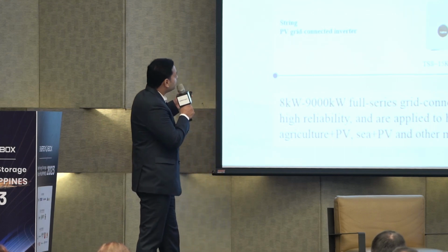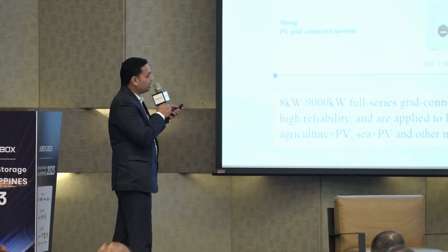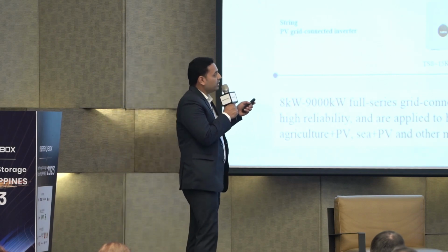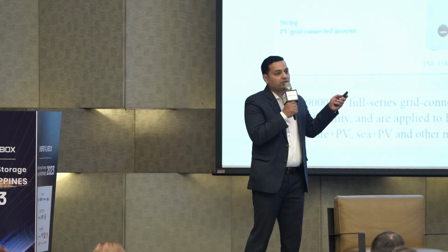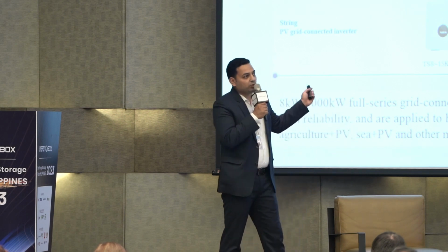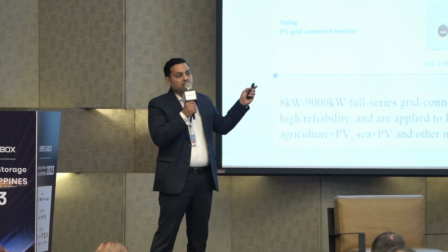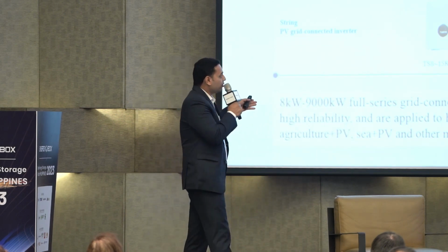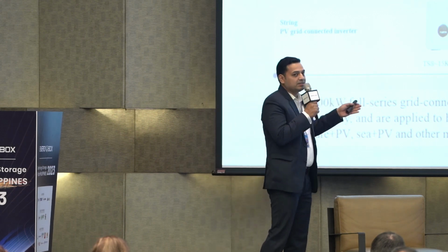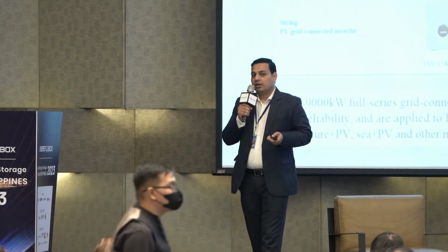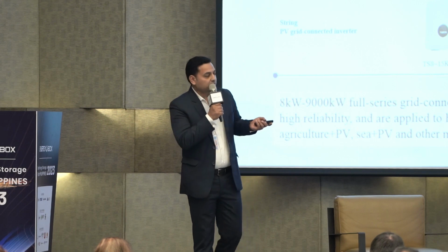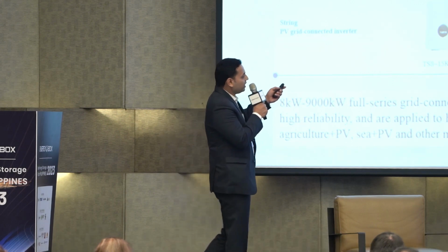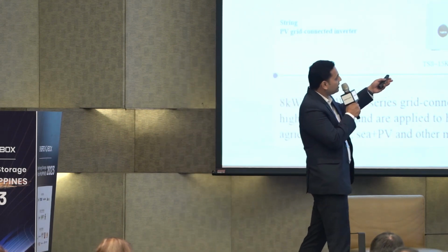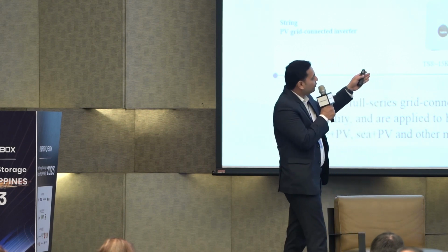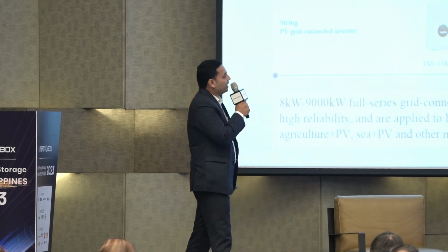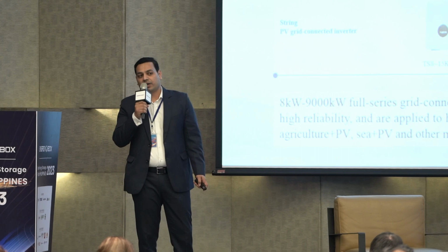For central solutions, we have two inverters. One is 3.125, the second one is 4.4 megawatt single unit. However, both these models are modular in nature. They have different numbers of modules. For example, 3.125 consists of two modules, which is 1.5 megawatt each. Similarly, for 4.4, we have three modules. As you can see in the picture, there are three modules in the cabinet, and each module capacity is 1.5 megawatt.